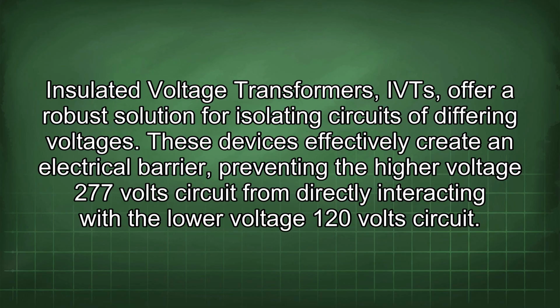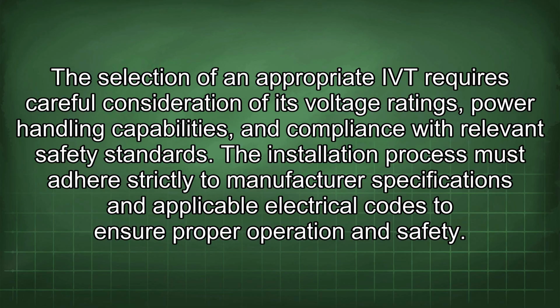Insulated voltage transformers (IVTs) offer a robust solution for isolating circuits of differing voltages. These devices effectively create an electrical barrier, preventing the higher voltage 277 volt circuit from directly interacting with the lower voltage 120 volt circuit. The selection of an appropriate IVT requires careful consideration of its voltage ratings, power handling capabilities, and compliance with relevant safety standards. The installation process must adhere strictly to manufacturer specifications and applicable electrical codes to ensure proper operation and safety.